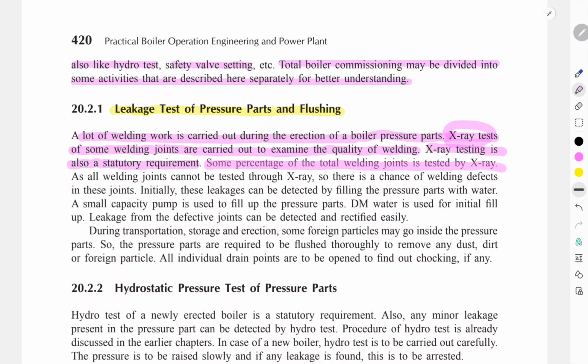is related to the leakage test of pressure parts and the flushing. The leakage test has to be done. A lot of welding work is carried out during the erection of the boiler pressure parts. X-ray test. Understood? The X-ray test will have to be done. Some of the welding joints are carried out to examine the quality of welding. The X-ray testing is also a statutory requirement. Some percentage of the total welding joints is tested by X-ray, as not all welding joints can be tested by X-ray. So there are chances of welding defects, and leakage in these joints can be detected initially by filling the pressure parts with water.